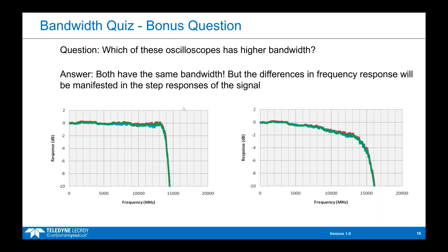Even though they have the same bandwidth, because they have a different frequency response they impact the shape of a signal differently. For example, with the oscilloscope on the left, frequency content at 10,000 MHz would see zero dB reduction in amplitude. But with the oscilloscope on the right, at 10,000 MHz of frequency content you would see almost 2 dB of roll-off in amplitude.